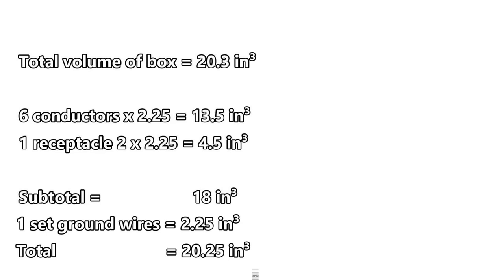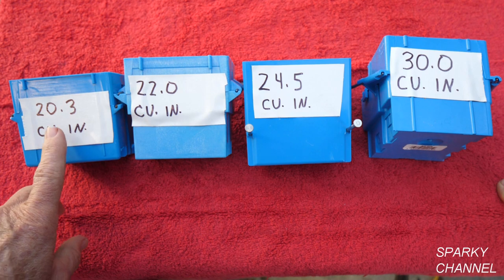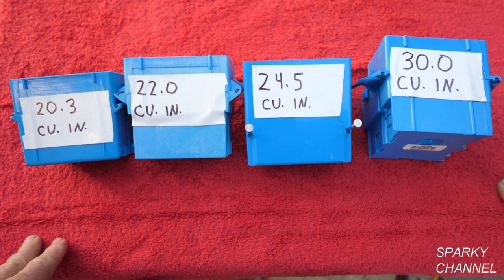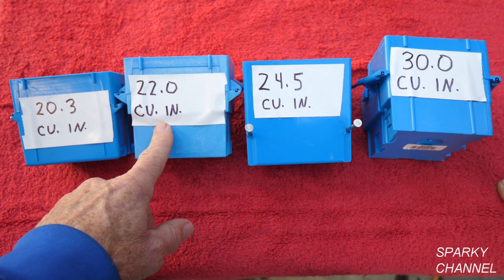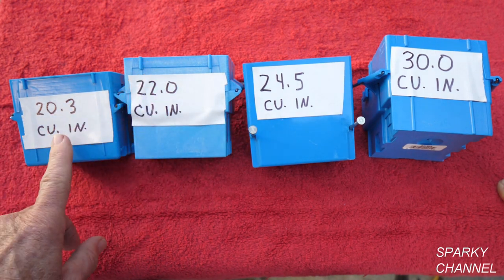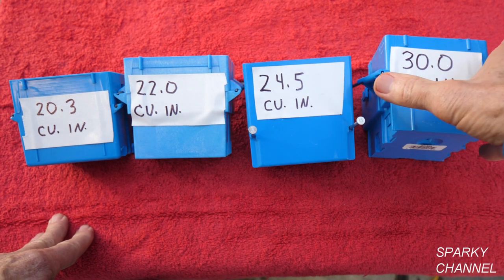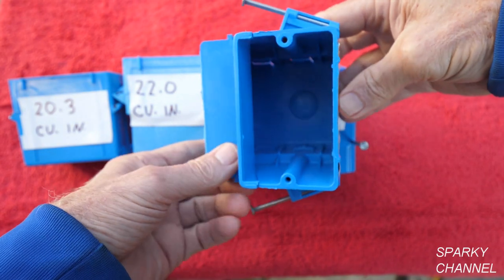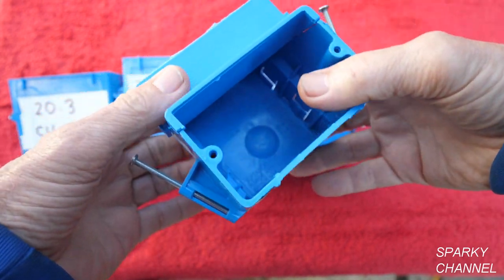This box passes! Now we know that you can put three 12-2 with ground cables and a receptacle in this 20.3 cubic inch box — but it just barely fits. What I really recommend is going with a slightly bigger box, like this 22.0 cubic inch or the 24.5 cubic inch, both made by Carlon. Both are a half inch longer than the 20.3 cubic inch box, but they do fit in 2x4 walls. And there's also this one that opens up with extra space — it's a single-gang box at 30.0 cubic inches, so consider that if you need a lot of space.